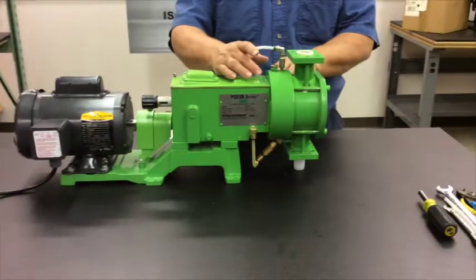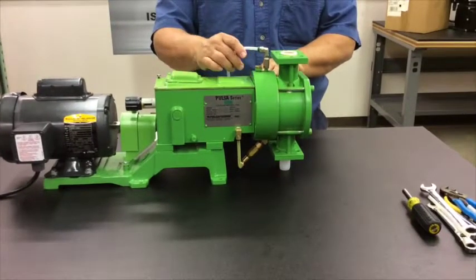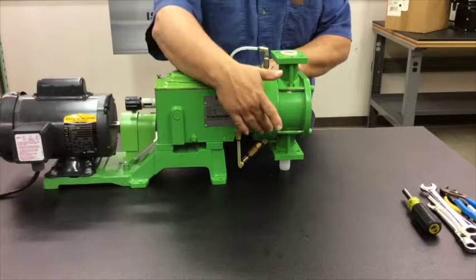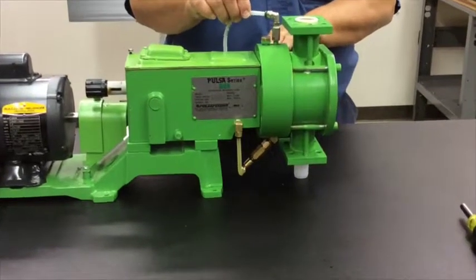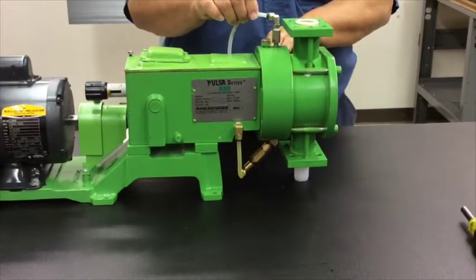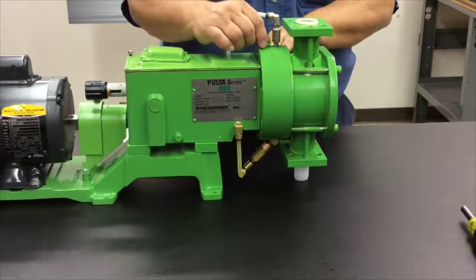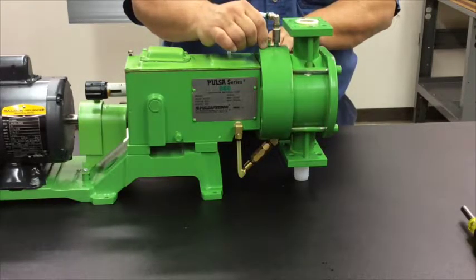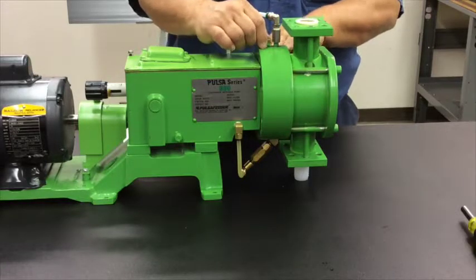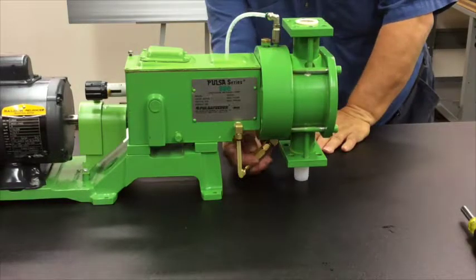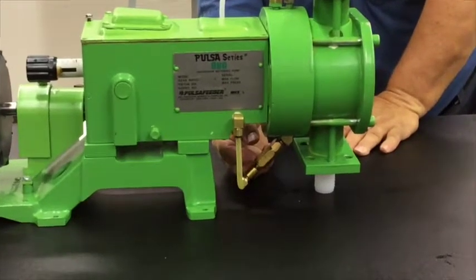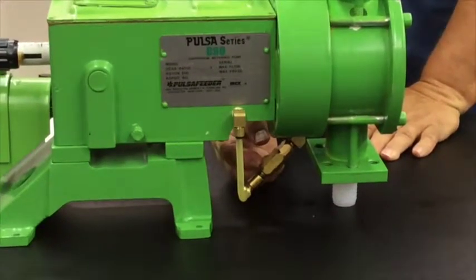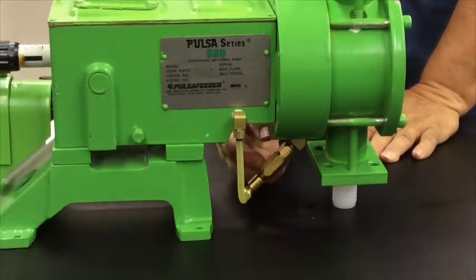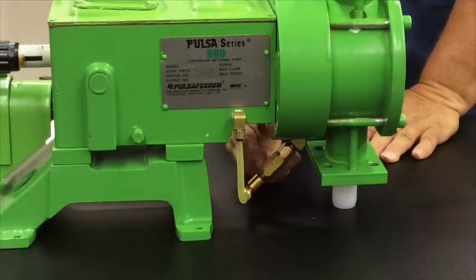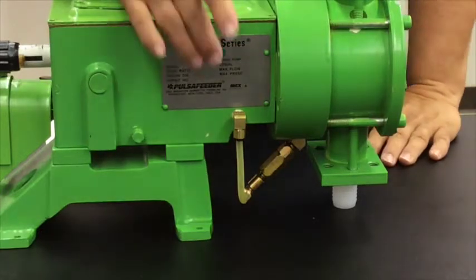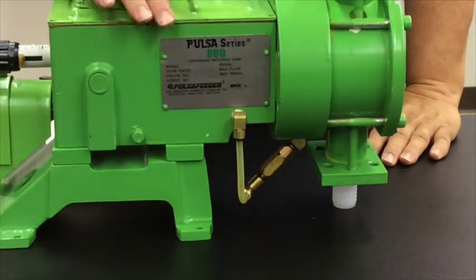So I'd like to now describe the major components of the pump head. This is the pump head here. At the top of the pump head is the automatic air bleed valve. Directly behind the air bleed valve is the hydraulic bypass adjustment screw. And then beneath the pump head, at the bottom here, is the automatic makeup valve. This is what adds hydraulic oil to the system, and it draws oil from the front chamber of the pump itself.